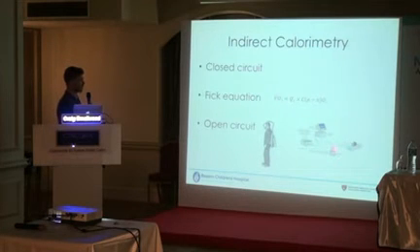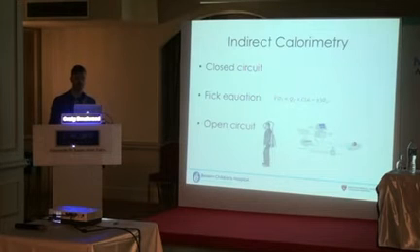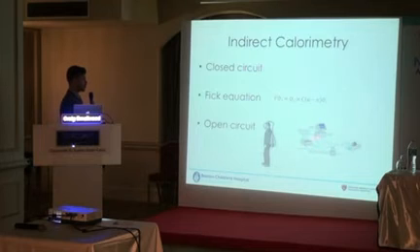So this is going to aspirate at a set flow rate, and it's going to measure the inspired concentrations of O2 and CO2 simultaneously. And then on the exhaust port of the ventilator, the patient breathes out through the ventilator, goes through the assembly that controls PEEP and measures the expired concentrations over here. And that's just really the expired flow. And so those are the 2 points of measurement.